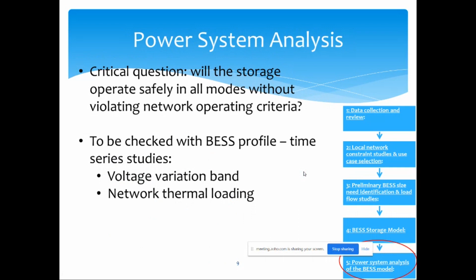There are several aspects that need to be checked. That's the voltage variation band - you want to ensure that when the storage operates, it remains within the safe band of voltage variation and doesn't cause issues on the network. The second one is thermal loading - will it cause strain on the network when it charges?